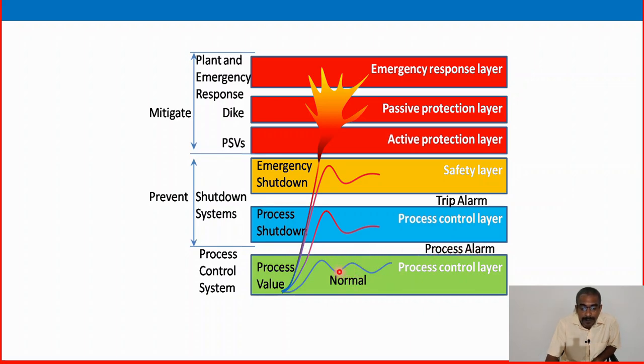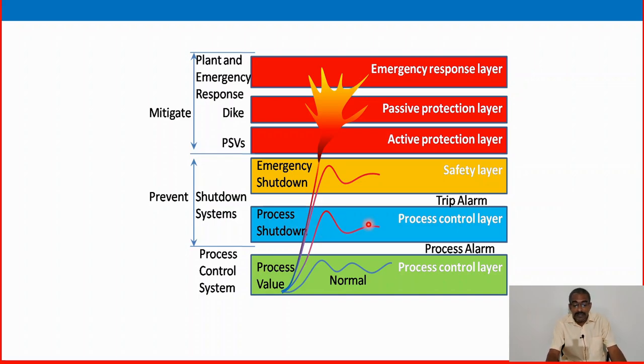Once the process variable is varying or moving up and down from the set point, the process alarm comes. The process alarm is crossing the normal operating process value — that is the process control system. Process alarm is just providing information to the operating people. There is no action on a process alarm. But when a process trip comes, some automatic shutdown or automatic trip occurs — stopping equipment, closing open valves, or opening closed valves.